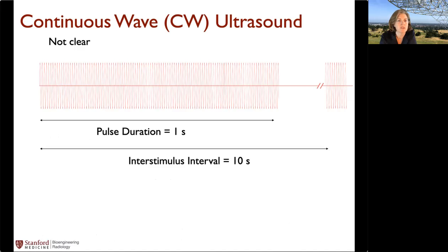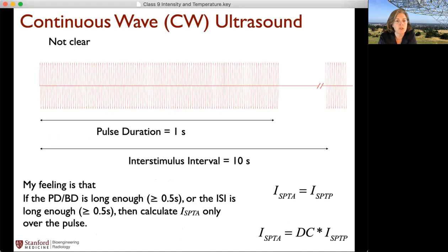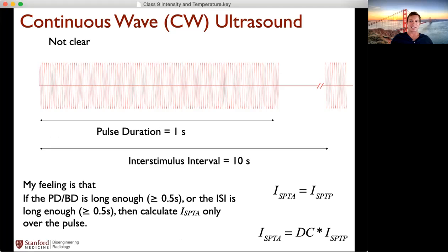But the reason I say it's not totally clear is that you might be in a situation where you have a pulse duration which is maybe kind of long, maybe about 1 second, and your interstimulus interval is 10 seconds. In this situation, I personally think that we just need to count over the pulse duration and not derate it for all that dead time when nothing is happening. Then our ISPTA equals our ISPTP. Because there is so much ultrasound on during this time, there could be heating, even during the pulse, and to derate it for the time period after that seems like it's not really fair.